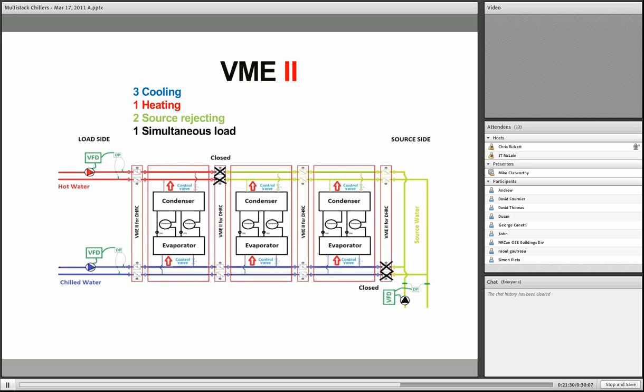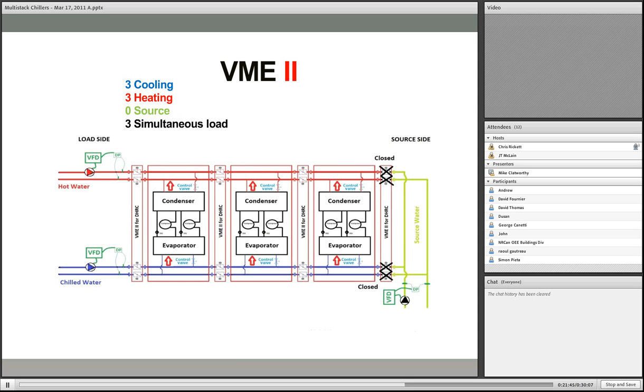In this scenario, it's a hybrid of what we saw, 3 in cooling and 1 in heating. So I have a little bit of simultaneous load. So I close this set of valves, and I'm rejecting the heat from the 1 module to the heating load, but I still need all 3 in cooling. Close this set of valves, all my chilled water is over here, and the heat that I couldn't use on my heat load goes into the source sink.